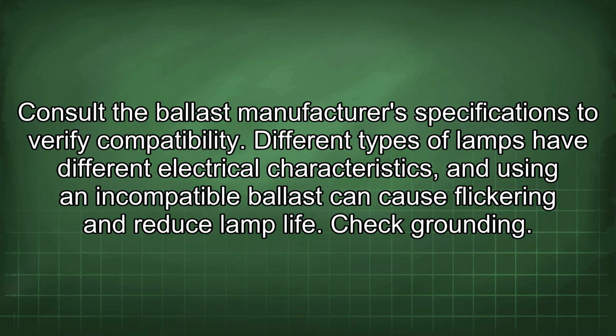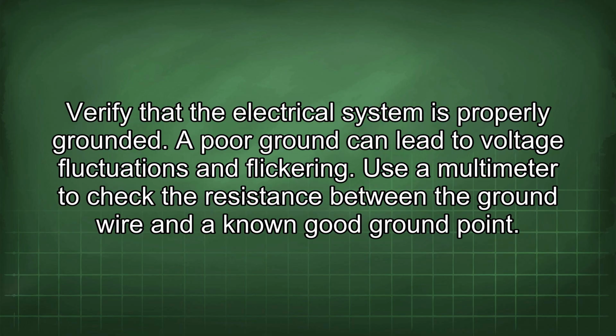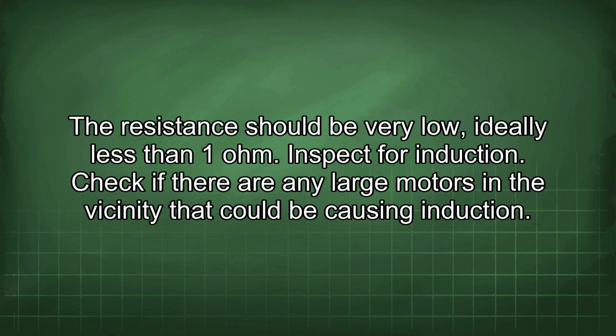Check grounding. Verify that the electrical system is properly grounded. A poor ground can lead to voltage fluctuations and flickering. Use a multimeter to check the resistance between the ground wire and a known good ground point. The resistance should be very low, ideally less than 1 ohm.